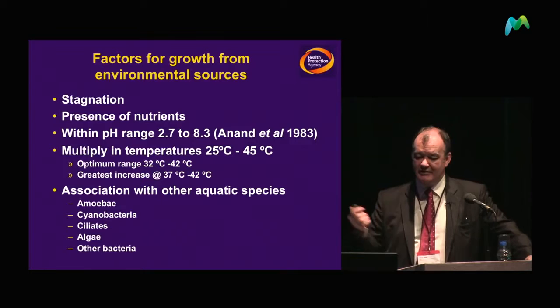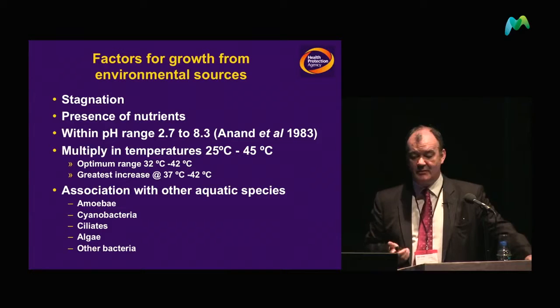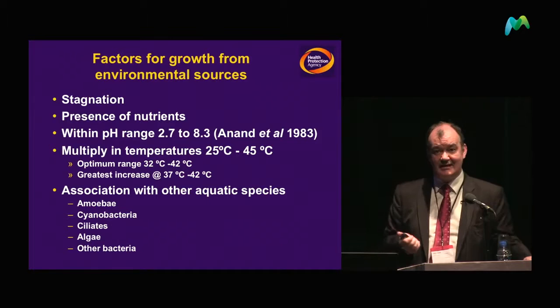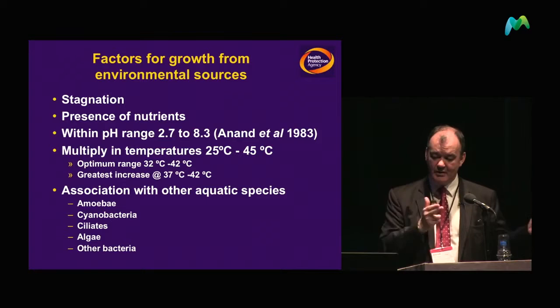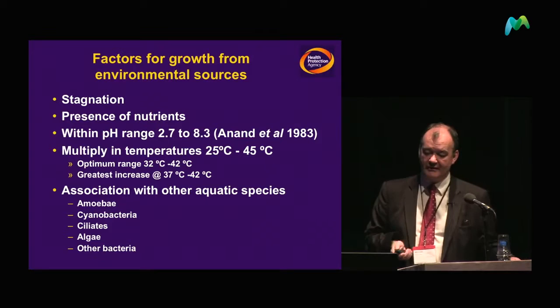Moving on to environmental factors — five elements are fairly key to the survival of Legionella in the environment: stagnation, where any pooling water is a potential source; nutrients; a fairly wide pH range tending toward the acidic; temperature, critically between 25 and 45 degrees; and association with other aquatic species.